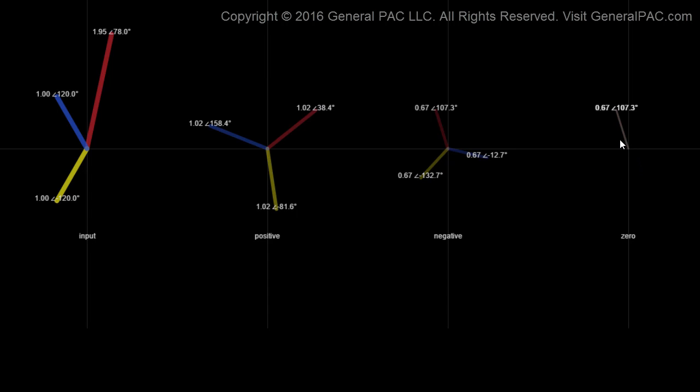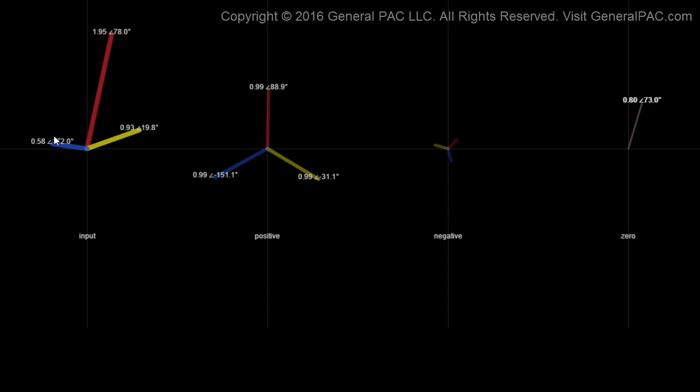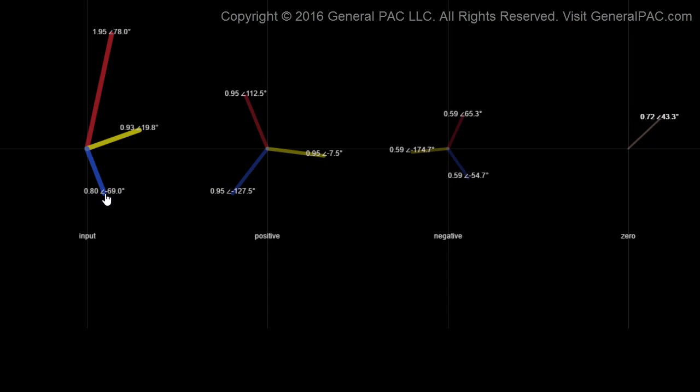Our zero sequence component has no phase sequence, and here it doesn't actually show all three phasors. But you can imagine that all three phasors are overlapping each other and have the same angles — so this right here would be just our zero sequence component. As we continue to move our phasors, we see that the sequence components all change to decompose the unbalance of our system. Now let's put it back to a balanced system.